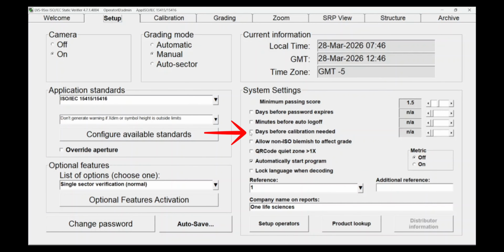this box here to have regularly scheduled reminders to your users to perform the field calibration. Use the slider bar or arrows to set the number of days between reminders. As I mentioned before, we suggest every 2 to 3 weeks depending on how dirty your environment is. This completes the guide to field calibrating your LVS 9510 verifier.